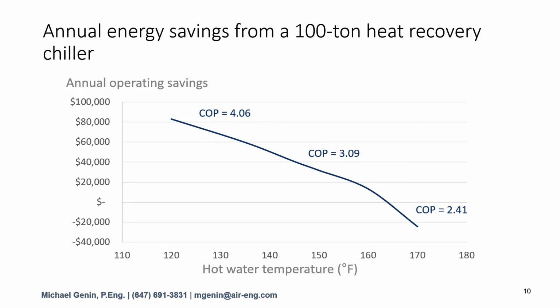Some might say that these numbers look great for a lower water temperature of 135 degrees in this case, but what happens at a hotter water temperature? Doesn't the efficiency decrease, resulting in a poor ROI? So I prepared this graph of the hot water temperature and operational savings. This is for a 100-ton chiller.